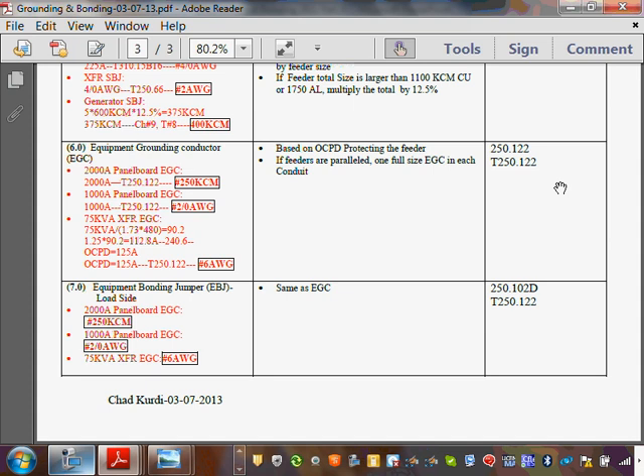In every set. Okay, so right underneath it, guys, this is the technical term for this baby. It's called equipment bonding jumper, and always use the load side. Where do you find this baby? Right in here, 250.102(D). You go, here's my 1000 amp panel. How do you size it?